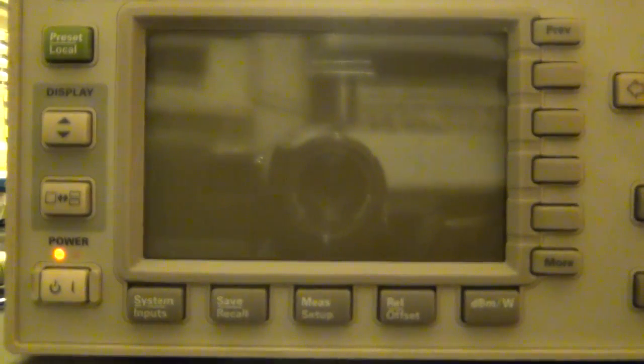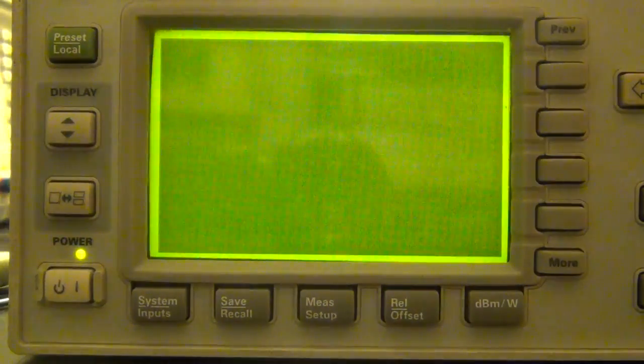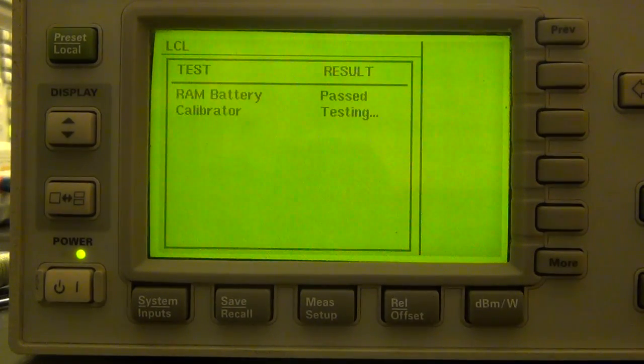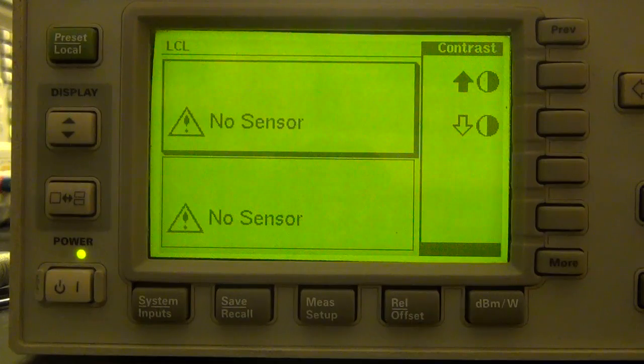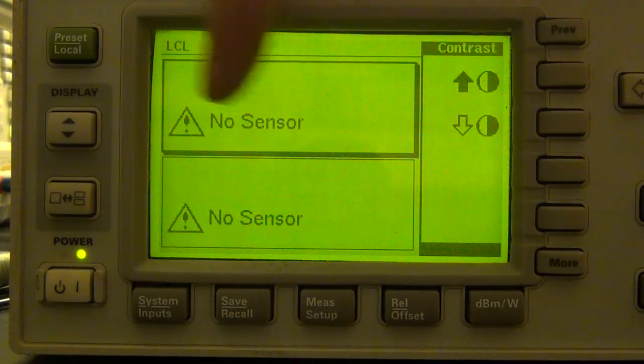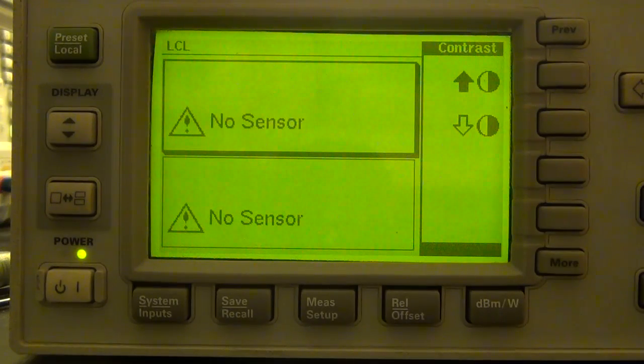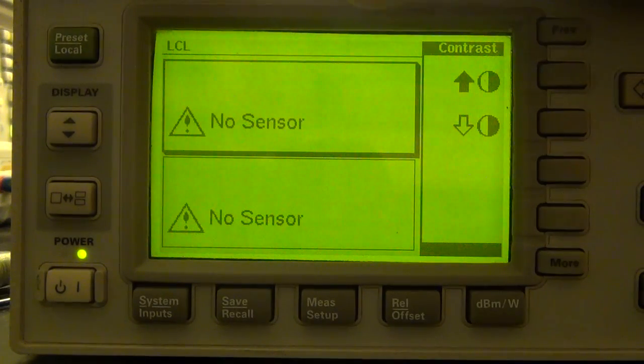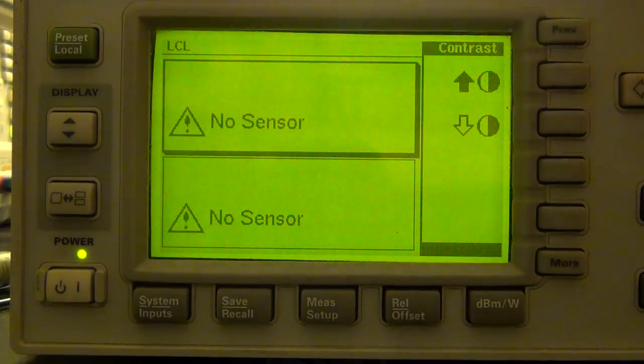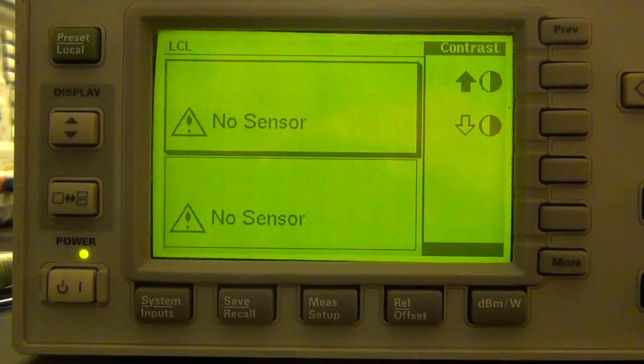All assembled and put together. Let's turn this thing back on. Now it's booting: battery test, calibrator passed, measurement assembly passed. So it passed all the self-tests. That doesn't mean it's going to work yet, because I have to connect the sensor to it and make sure everything looks good. But first I want to tell you a little about how the sensor looks, and take one apart for you before we verify the performance of this unit.